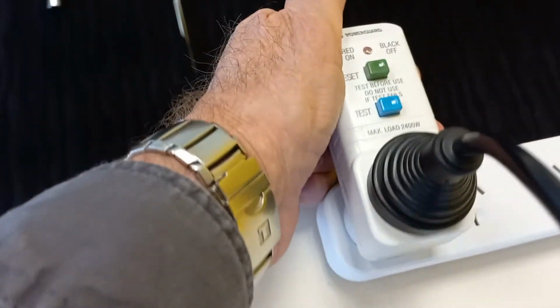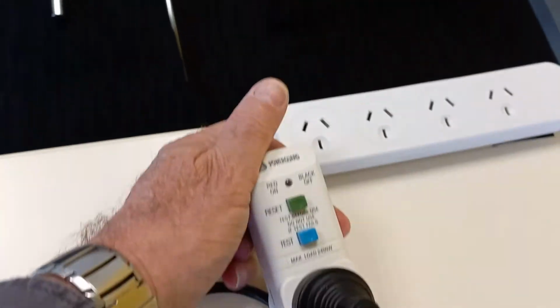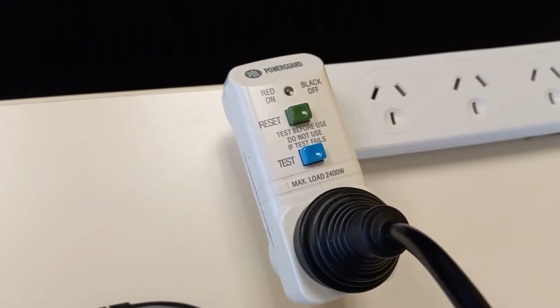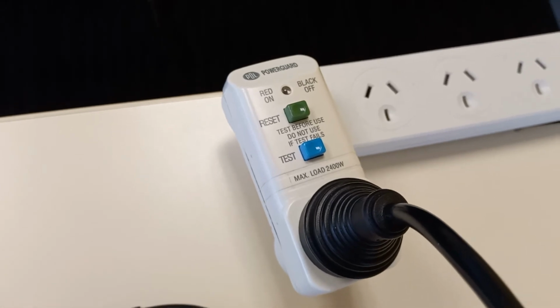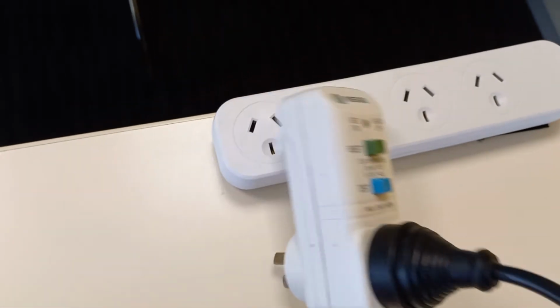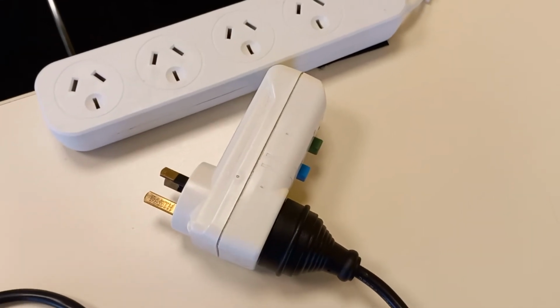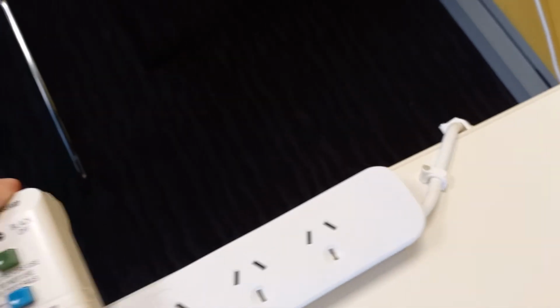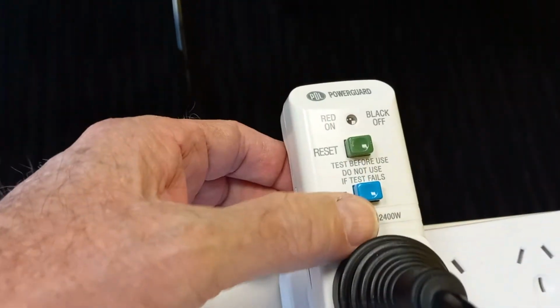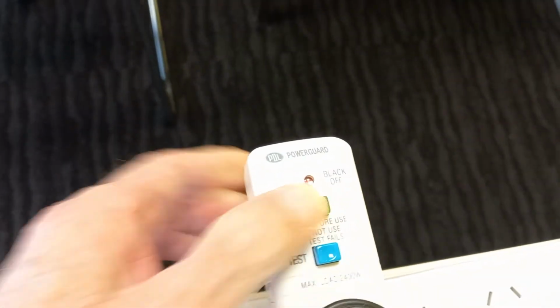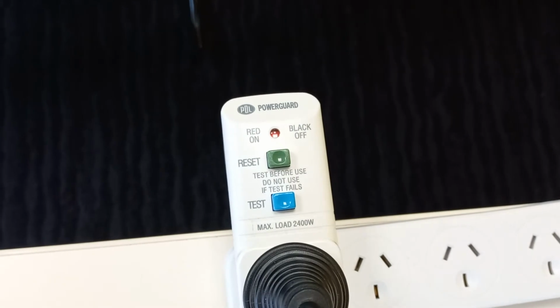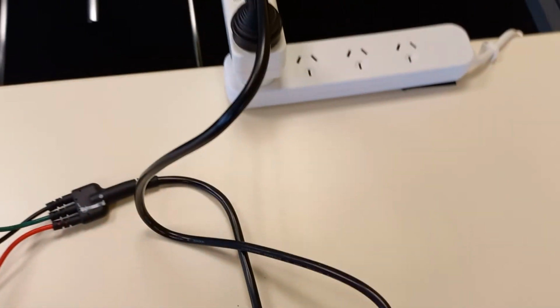One of the functions also of the portable RCD, when resetting it, is that if I unplug it, it trips out as well. I've got a double pole switch in here to switch out the phase and the neutral conductors. So that is another way of testing that this is not frozen, just by removing it from the supply, and it drops out. When I reconnect it to the supply, it's a 230 volt 50 hertz supply, I have to do the reset first to energize and close the two contacts and provide power output to my appliance.